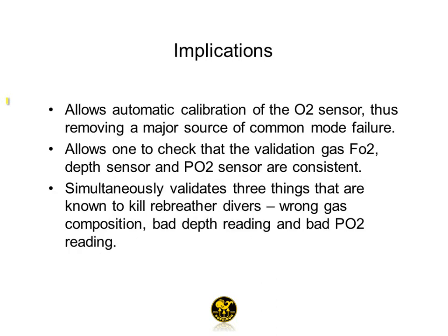First, it allows genuine automatic calibration of the oxygen sensor. What we do on the Mark VI is take what you've told us is pure oxygen, or actually, it doesn't have to be pure, but you've told us that this is oxygen with a certain fraction of oxygen in it. We calibrate the sensor against that. We then automatically inject the diluent across it. And if it doesn't come in absolutely where it should be, then one of two possibilities: you don't have oxygen, or you don't have the diluent you told us.